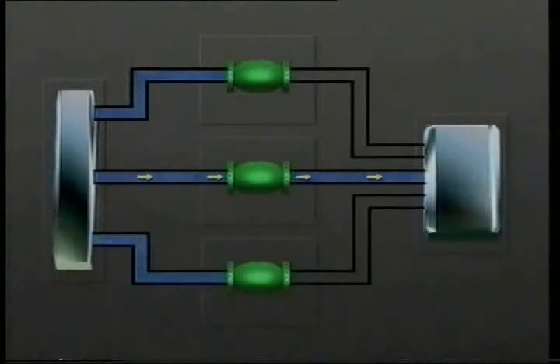Another factor is to keep apart any parts or systems which are doing the same job. For instance, if a pump has 2 backup pumps, they are at different locations so that fire or flood cannot affect them all. In the same way, electrical circuits follow different routes.